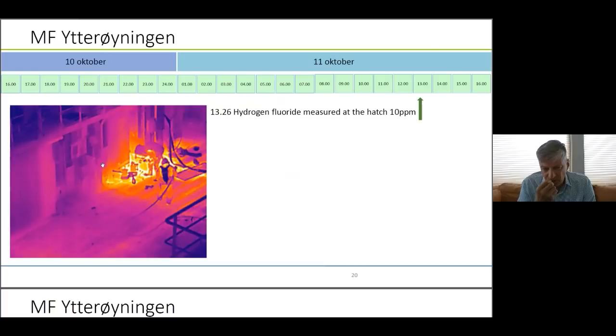When they go down, you can see one firefighter watching the other. The other one is in a chemical suit, and they measure 2 parts per million just down the hatch, and 10 parts per million hydrofluoric acid in the battery room, with the temperature at 70 degrees. So they do some recordings and go up again.